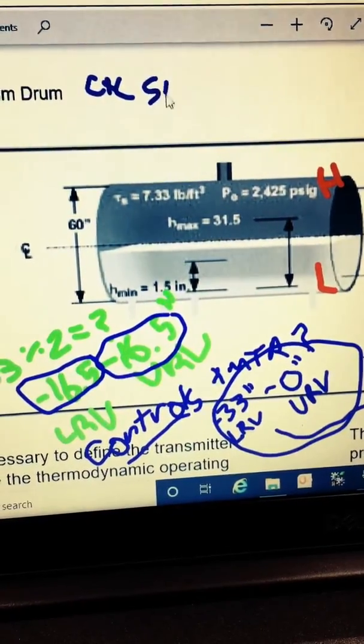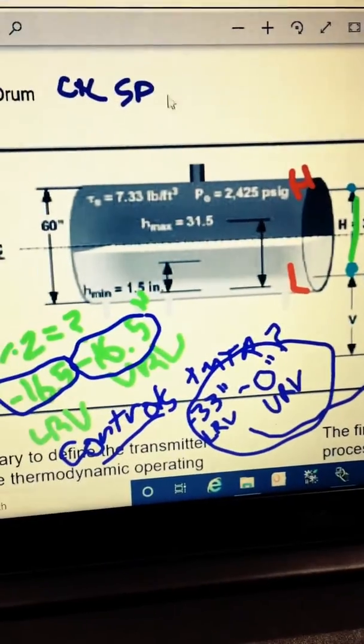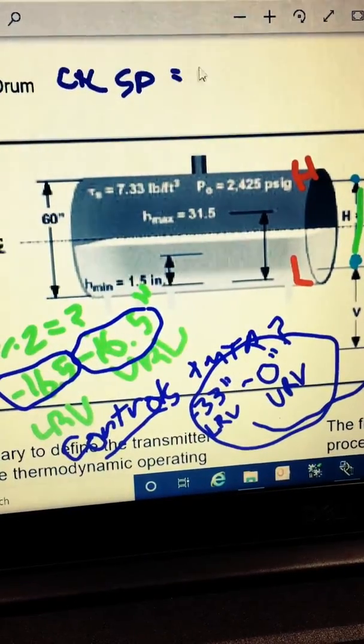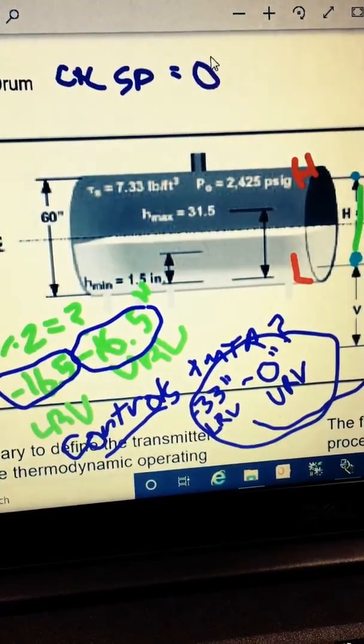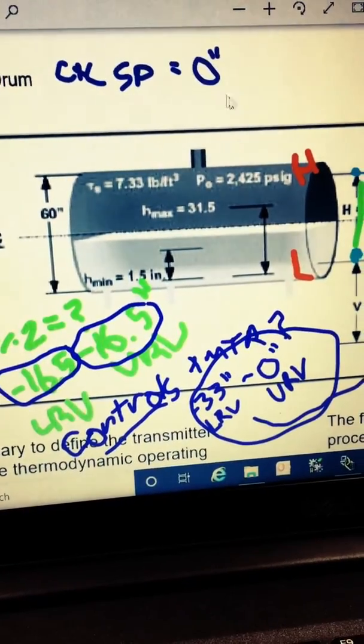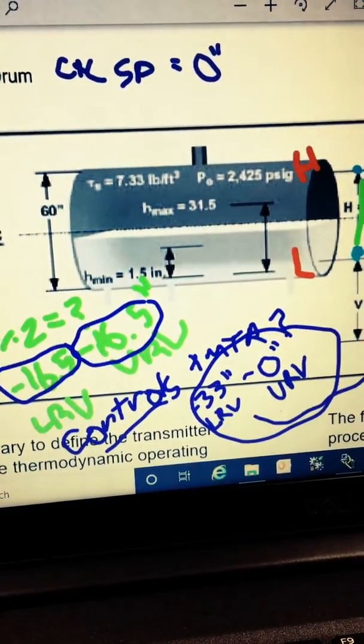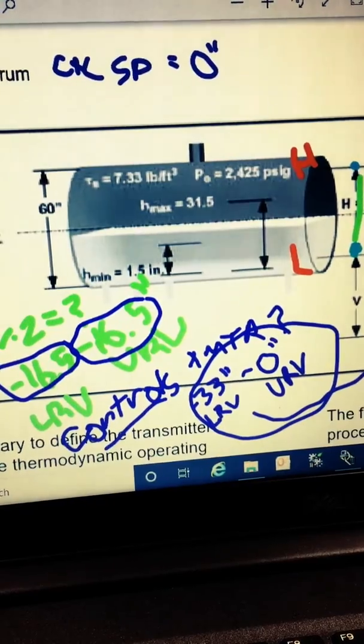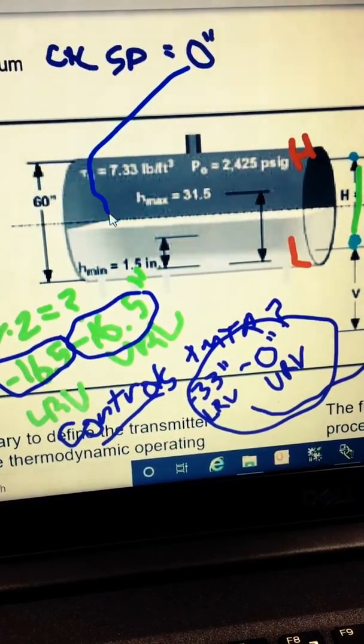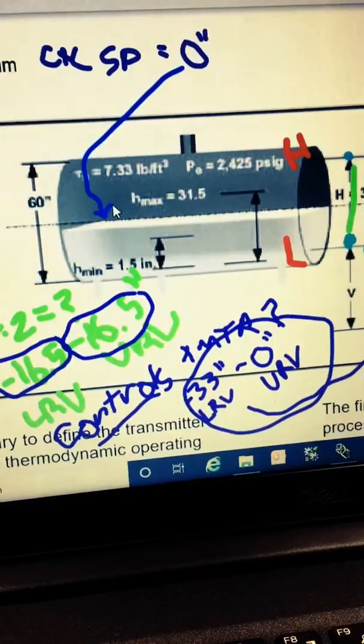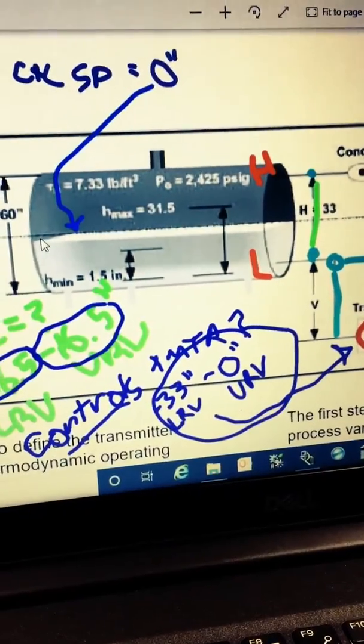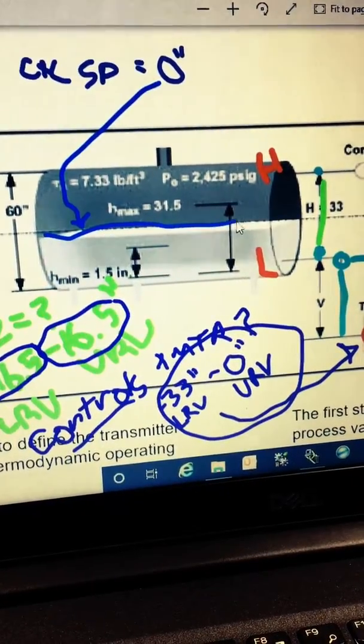And the reason you're going to do that is because you ultimately want zero to be the nominal level that you're trying to control to, zero inches, which would be, in theory, 50% level. So your control set point would be zero inches, which should give you a level that basically was at the center of the drum.